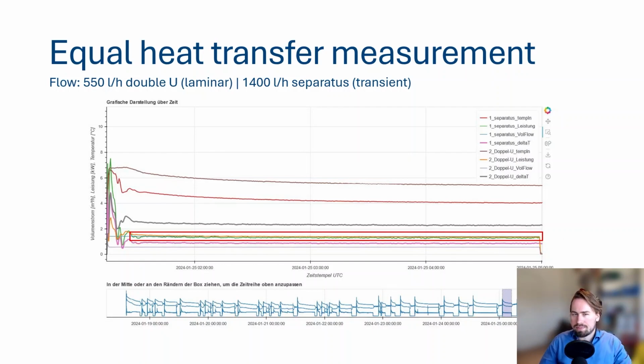Now, if we do so, we know since Separatus and GHEtool have the same borehole effective resistance, we can use GHEtool or Earth Energy Designer to calculate the parameters, or we can use the model with the GHEtool in order to calculate the borehole effective thermal resistance. And given that number, we can reverse engineer what parameters we should take for the single U-tube in order to come up with the same effective resistance. And this is what they did at Separatus.